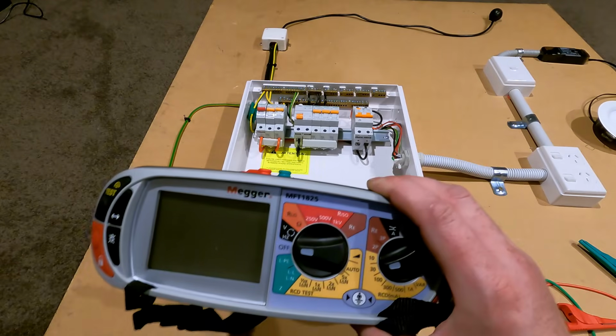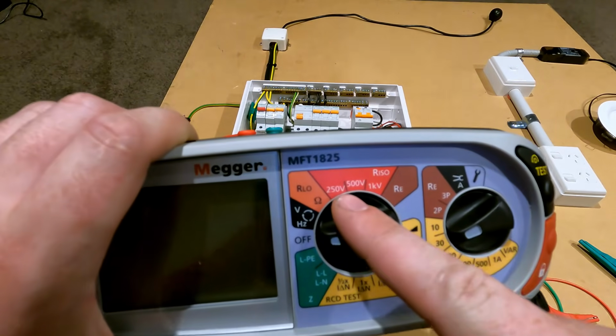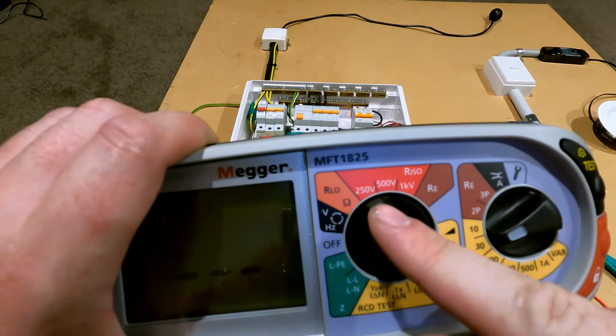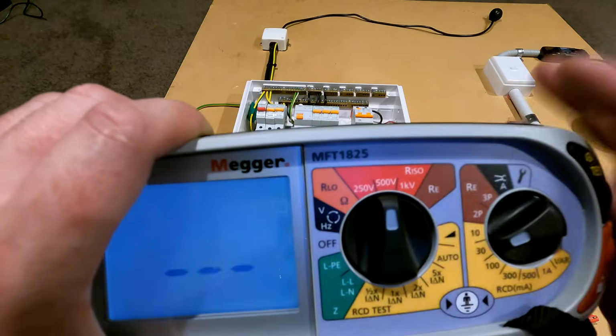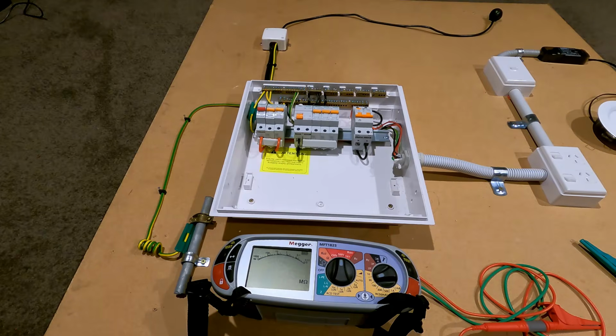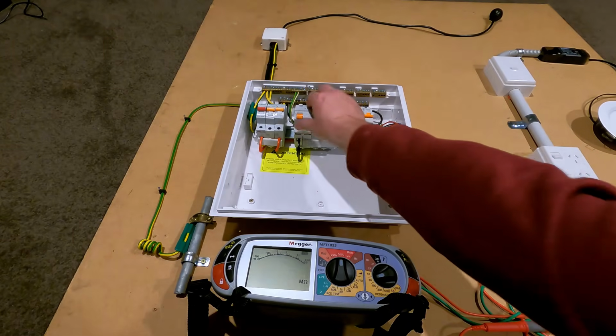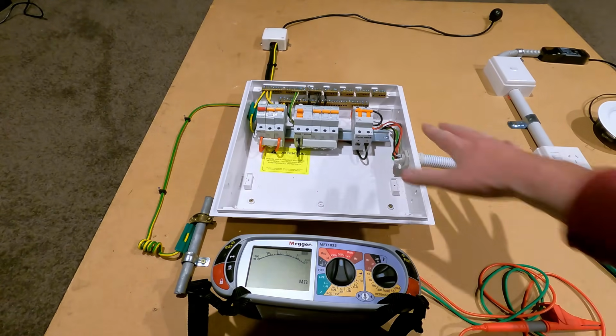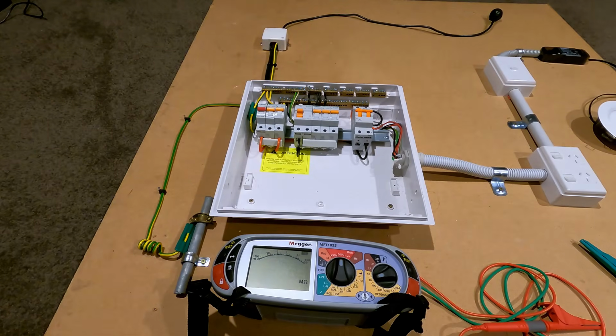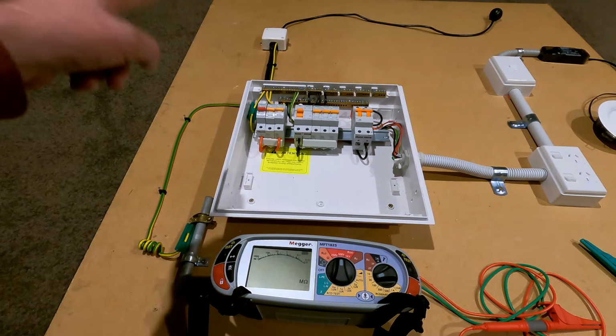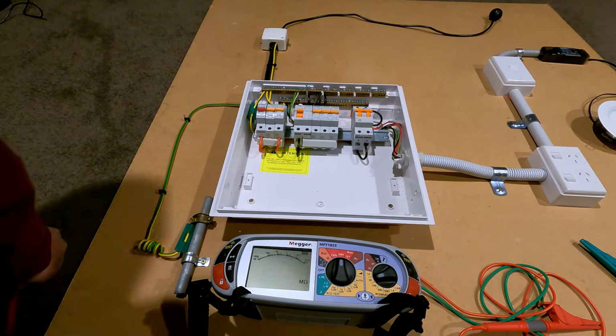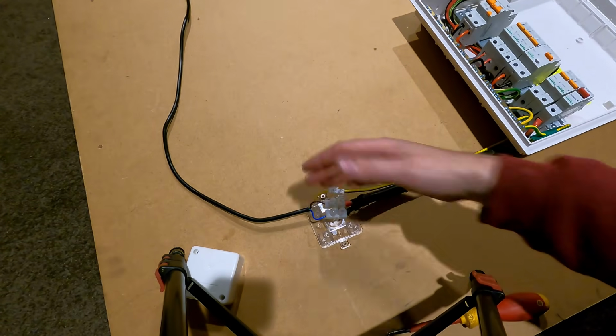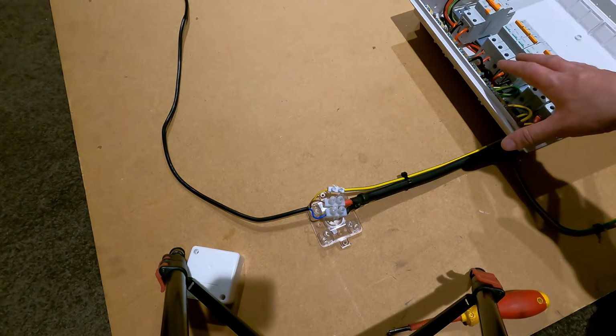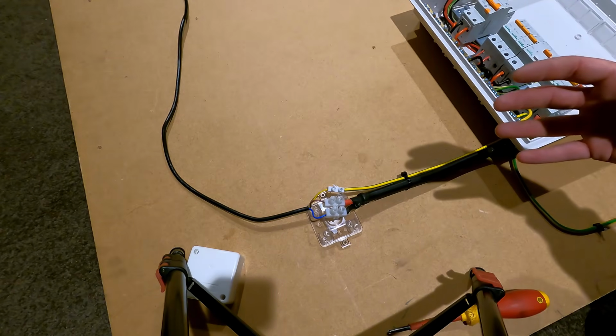Now when we do our insulation resistance test, you'll see on the Megger here, it's just simply turning the dial to these red indicators. Now we need to stress the cables at 500 volts DC. The easiest way to do this is to turn all of the circuits on, including your switches, and then we're going to directly short out on the end of our line connection out in the meter box. So I've set this wee connection up just so I can simulate having this installation live and going through the live testing for you guys.